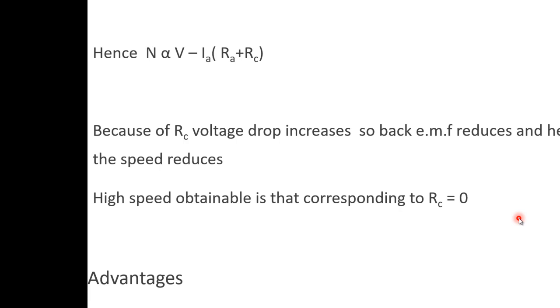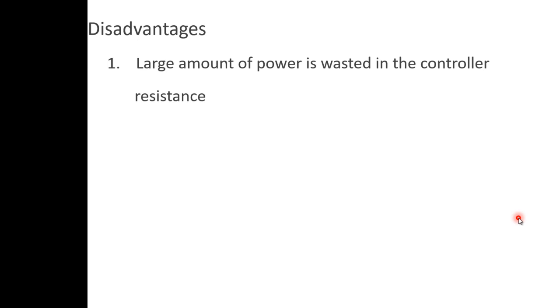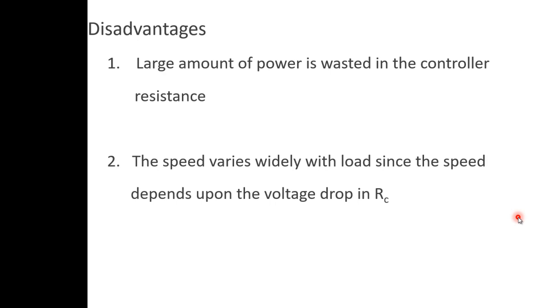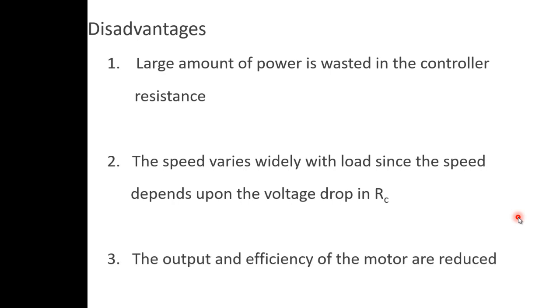The speeds obtained using the rheostatic or armature control method are all below rated speed. Disadvantages: a large amount of power is wasted in the controller resistance added externally in series with the armature; the speed varies widely with load since it depends on the voltage drop; the output and efficiency of the motor are reduced; and this method gives poor speed regulation. Compared to the field control method, the armature control method has many more disadvantages.